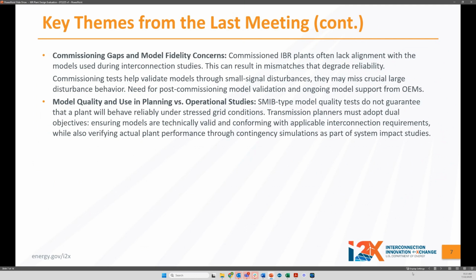If there are any discrepancies or differences, those get reevaluated after the interconnection and commissioning processes to make sure the models get trued up. The whole goal of IEEE 2800.2 - and Jens will talk about this - is that along the commissioning steps we produce data. The commissioning tests generate lots of data that can be used to validate the models, particularly for small signal disturbances: the bump test, voltage reference step test, frequency reference step test, ramp tests, and things like that.